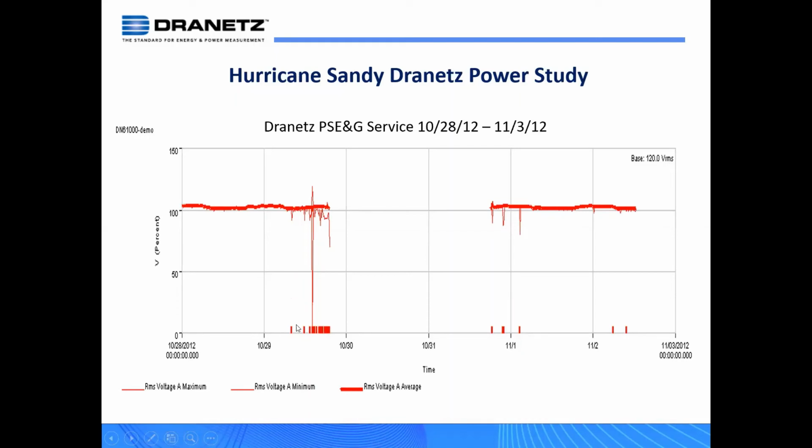And what it means is that at that point in time, the system recorded an event, or this monitoring instrument recorded an event. You may or may not see it here because it may not be an event that you're displaying at the moment, but you could see it recorded events at that period of time, and there's a plethora of data that was recorded here. So this is a Monday morning when the power went out.